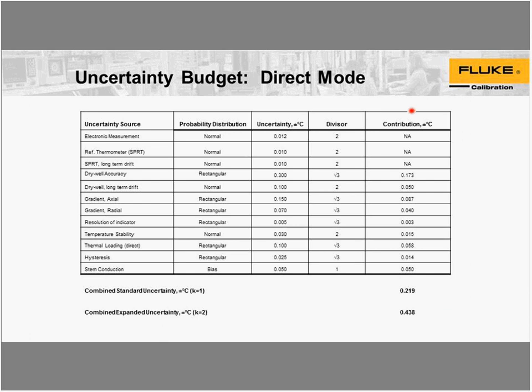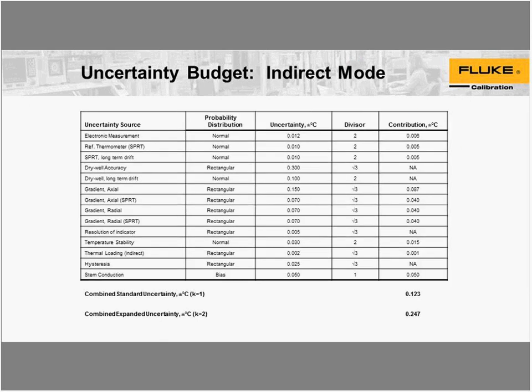If we compare that with the indirect mode, basically eliminating most of the thermal issues by using the indirect mode, and hysteresis is not a function of the dry well here at all, then we greatly improve our combined expanded uncertainty.